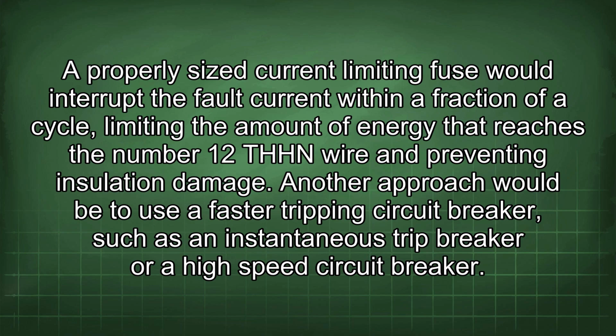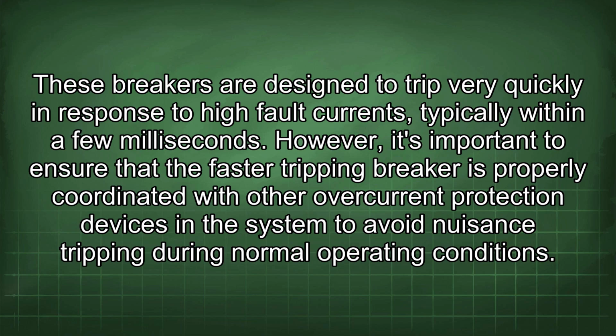Another approach would be to use a faster tripping circuit breaker, such as an instantaneous trip breaker or a high-speed circuit breaker. These breakers are designed to trip very quickly in response to high fault currents, typically within a few milliseconds. However, it's important to ensure that the faster tripping breaker is properly coordinated with other overcurrent protection devices in the system to avoid nuisance tripping during normal operating conditions.